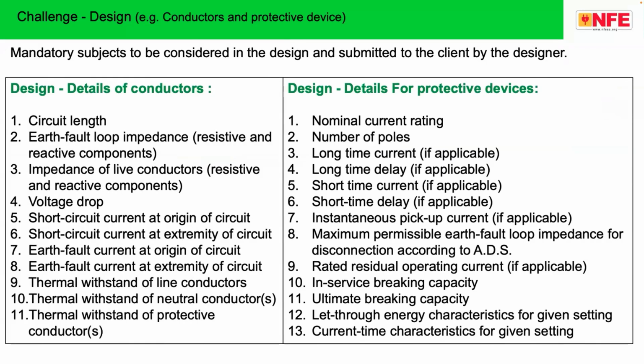When designing an electrical installation, the National Electrical Code says, I put this as a challenge in design. I just put the example of designing the conductor, and the design requirements of the protective device. Normally, when we ask the designers of a new hospital, for example, how did you select this wire? Then they say, depending upon the voltage drop.